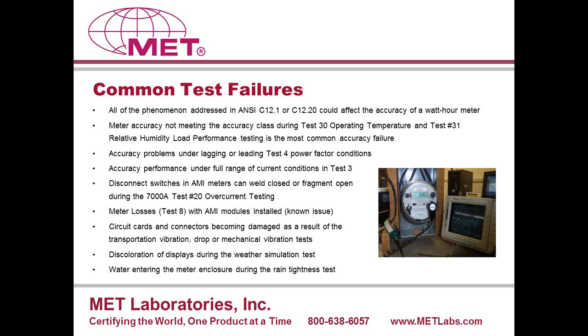Circuit cards, connectors, standoffs becoming broken during the transportation vibration or drop test. It's important to note there that really, if we see that, we will mention it, because the standard is not looking to call something like that a failure for those drop tests, for example. The pass-fail criteria there is that it's got to remain accurate. So essentially, we do a performance check both before and after these tests. Many times we'll see a cracked standoff or a connector that comes loose that doesn't affect the accuracy of the product in that condition. Then we call it a compliant. Of course, we're notifying the manufacturer of that because many times they want to address the issue. But just because something would crack, for example, doesn't necessarily mean during the drop test that it's a failure. So it really is dependent upon what the pass-fail criteria is out of the ANSI standard.